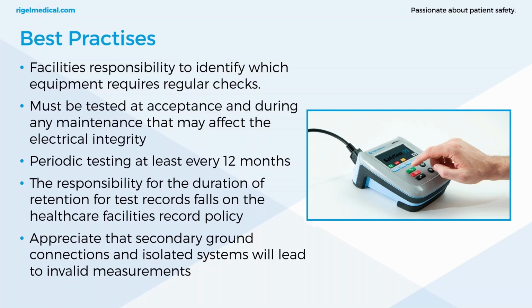So what are the best practices? It's the facility's responsibility to identify which equipment requires regular checks. Each device must be tested at acceptance in accordance with NFPA 99 and during any maintenance that may affect the electrical integrity. Best practice, every time you open up a unit and you make any changes, you just carry out a test. But there are also recommendations on the minimum periods for safety checks whilst in service, and we say that at least every 12 months.